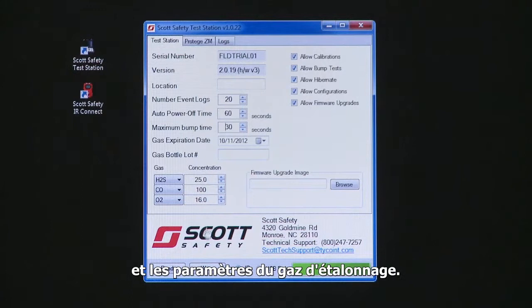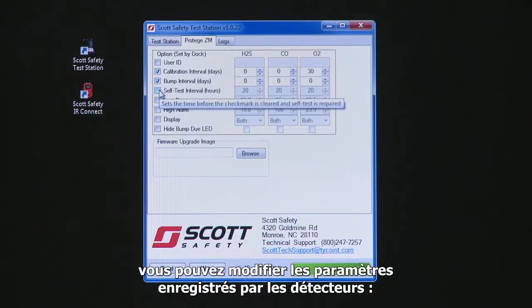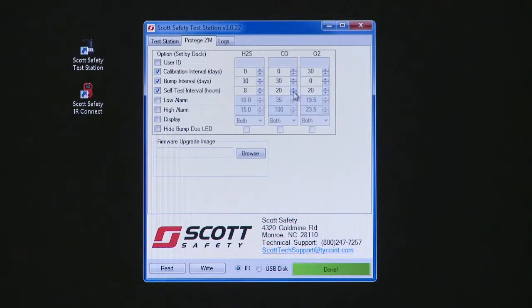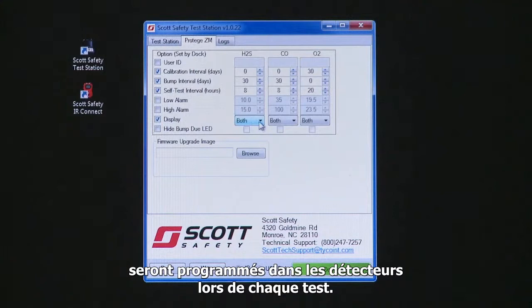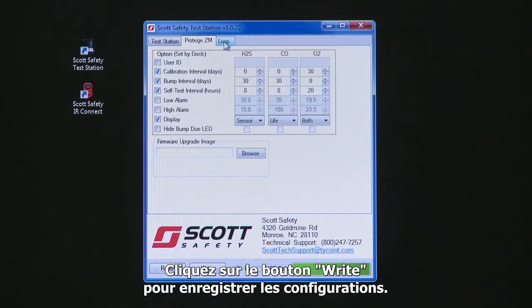On the Protege ZM tab of the application, you can change the settings to be stored on the monitors during testing. Settings include the calibration and bump intervals, self-test interval, display settings, and the low and high alarm settings. Items marked with a check mark will be programmed into the monitors whenever they are tested — a convenient way to ensure your monitors are always programmed with the latest settings. Click the Write button to save these settings on the test station. The Logs tab allows you to read the data logs stored on the test station and write them to your computer for safe keeping.